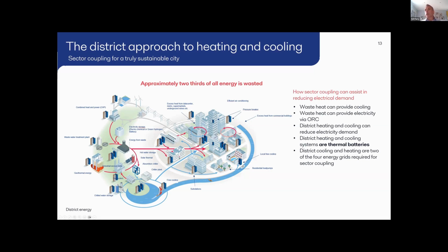Because as a generality, renewable energy sources normally struggle to modulate based on demand at any kind of speed. They like constant demand that they can churn away at for long periods of time. And the thermal storage aspect allows you to do that. Because of the diversity that's applied in the sizing for both heating and cooling, that also allows you to have less as a total demand, because the buildings simply won't require all cooling at the same time or all heating at the same time. So there's diversity applied to that. And of course, a really important point is that the waste heat can also be utilized via ORC plants to give you electricity. And as I say, the pipework becomes that thermal battery. And there are many studies that show by far and away the cheapest form of energy storage is thermal storage.